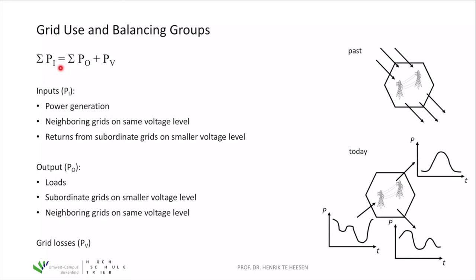This power balance equation must always be fulfilled. If there is more power input than output, the frequency increases, so the operator decreases power generation. If output exceeds input, the operator can increase power generation or reduce loads. Balancing this equation — ensuring input and output are in balance — is the main task of TSOs and operators at every grid level.